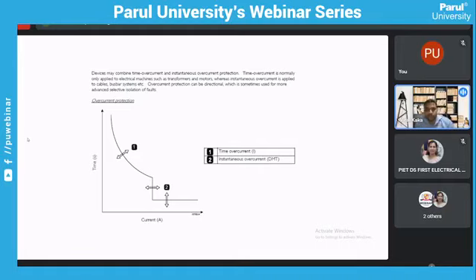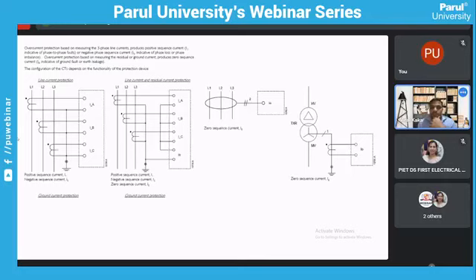So normally, time overcurrent relay applies to an electrical machine, such as a transformer or motor. But again, the differential protections of the transformers are meant to act as fast as possible. Instantaneous overcurrent protections can be directional, which is used sometimes in more advanced selective isolation. So there are systems where you need to apply a directional overcurrent as well whenever you are running a system in parallel. Let's say you have an incomer and then also a connected generator, and then there are chances of seeing the fault in the reverse direction or in the forward direction towards the other end as well. So that's why the directional feature also plays an important role in the power system.